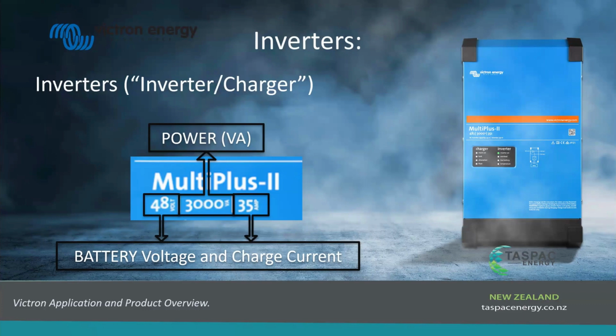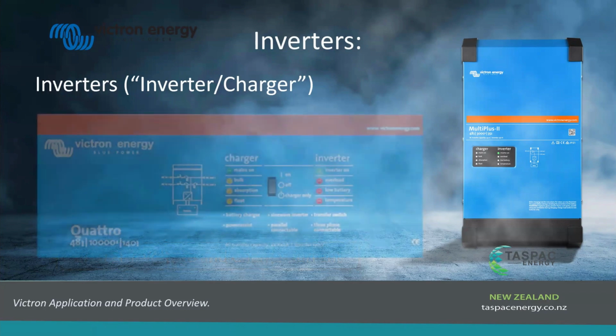Gen 24 inverter. Now, bear in mind, if you're going to AC couple, you need to make sure the AC coupled inverter is below or equal to the power rating of the Victron inverter. So if you've got a Multiplus 2 48-3000, which is this one, you can only put a 3 kilowatt Gen 24 on the output of that inverter. You can't put a 10 kilowatt Gen 24 on, or this little inverter will start trying to jump off the wall and into a cold pool, or it will just end up smoking, which is bad for you.